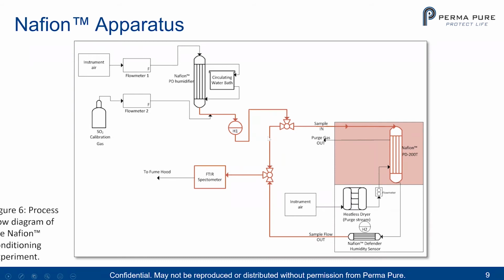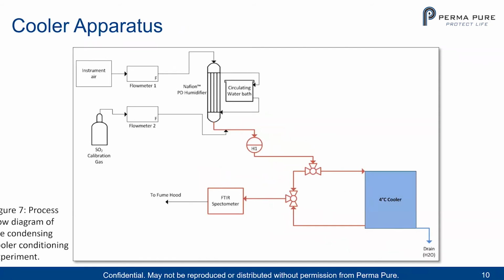Right? With these valves here we can control directly what's going into the FTIR. We can use the gas that's coming right off of the calibration section. So we know that that's test gas A, and test gas B is the gas that has gone through the Nafion dryer. Similarly with the cooler, we use our same calibration gas humidification setup here, and then instead of our sample gas, we're using the cooler and doing the same thing where we can A/B test before and after. Okay.